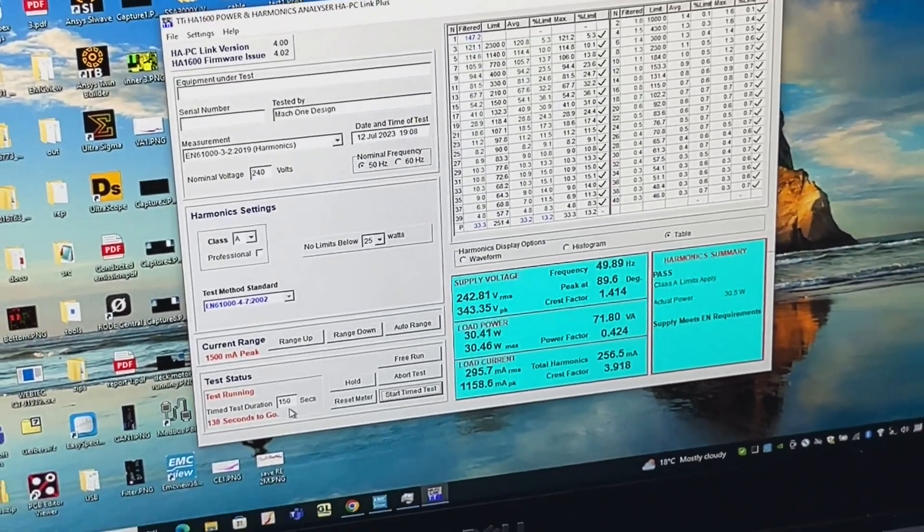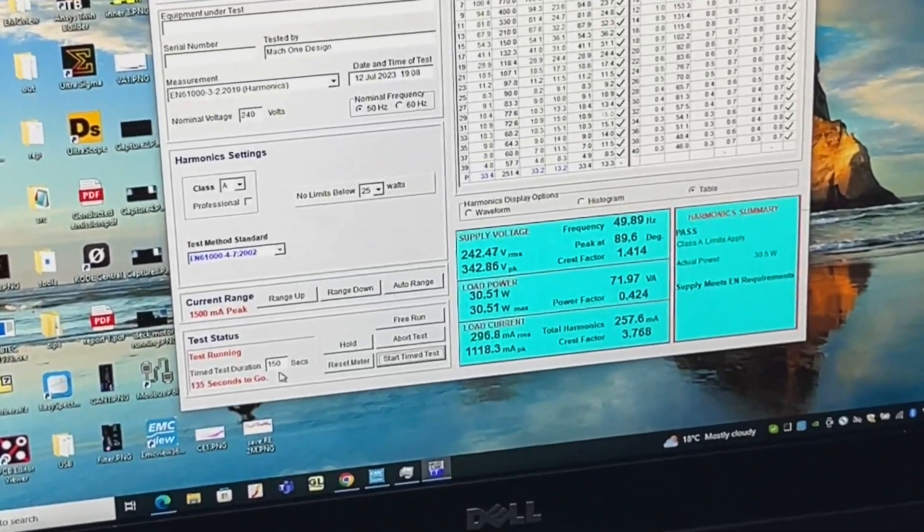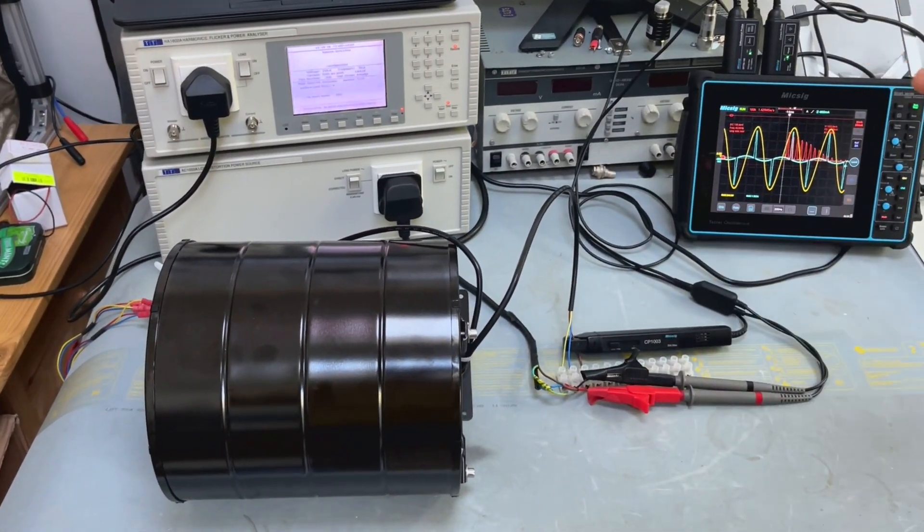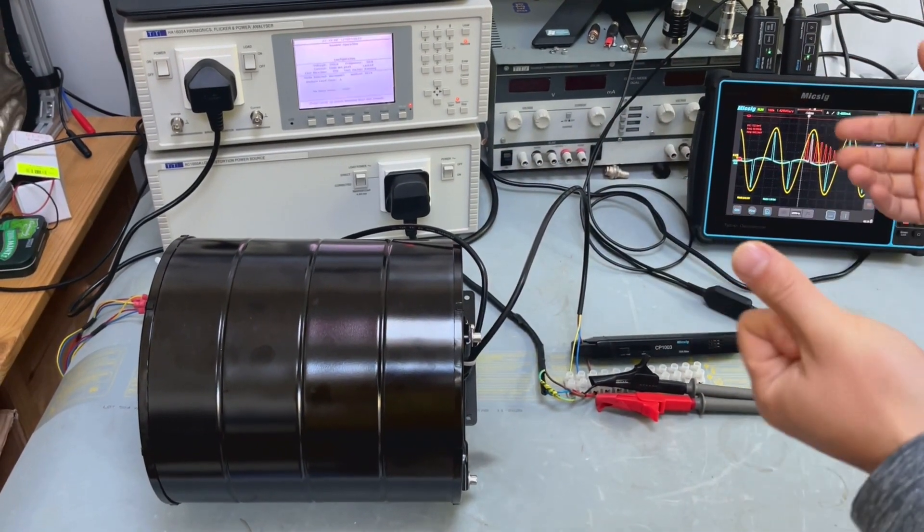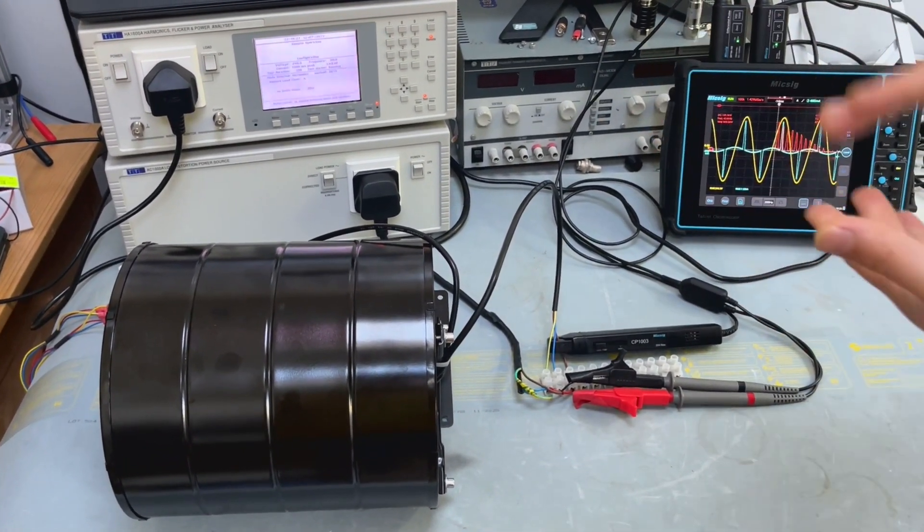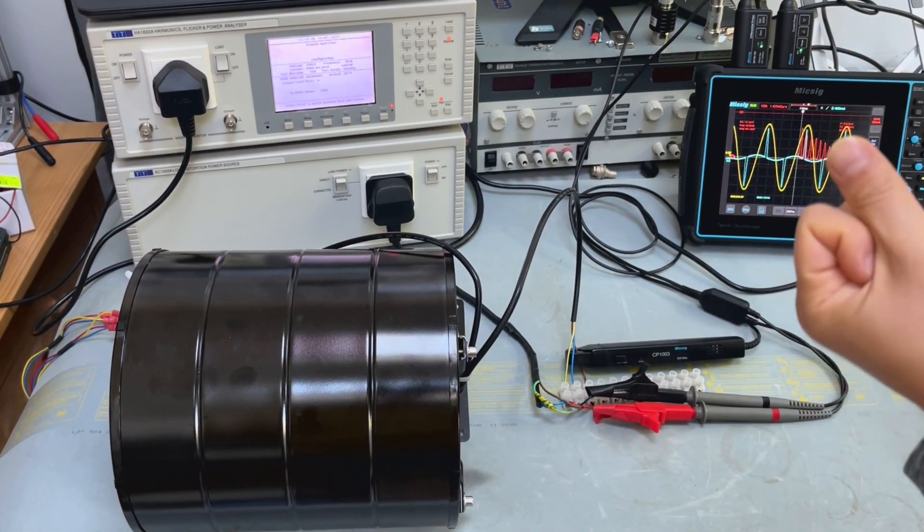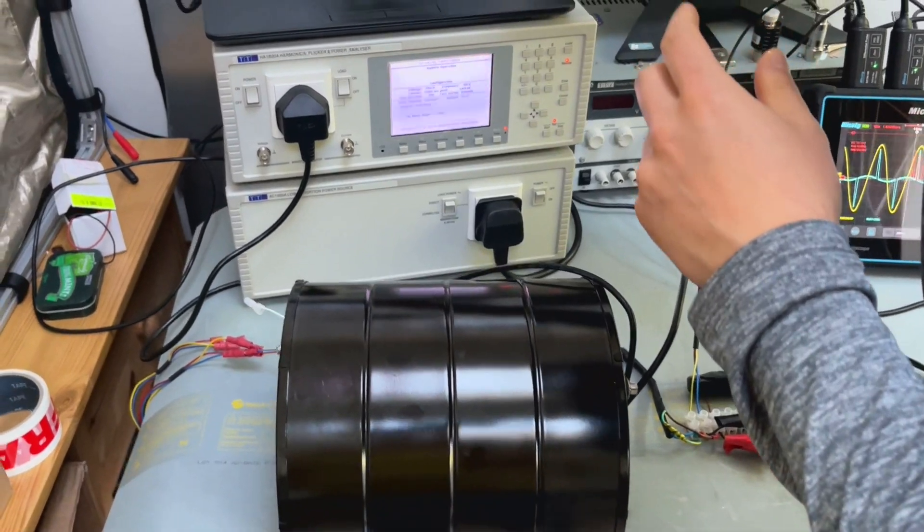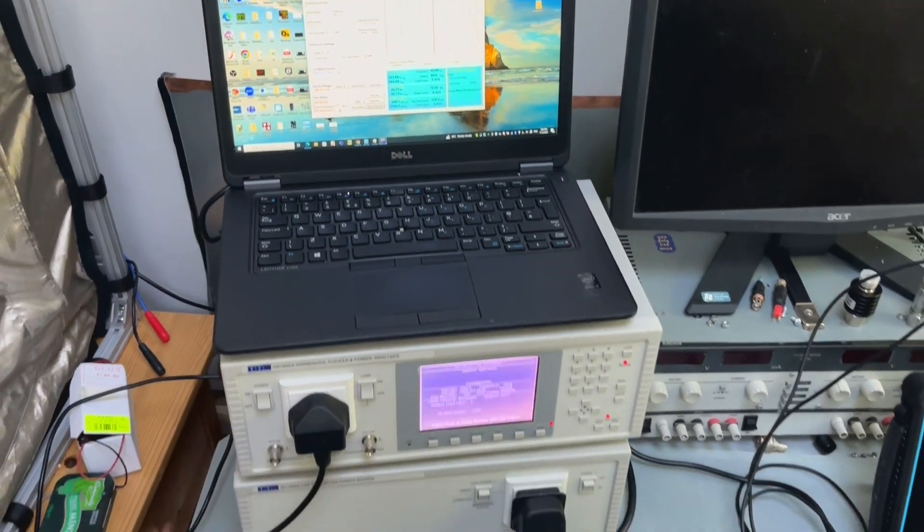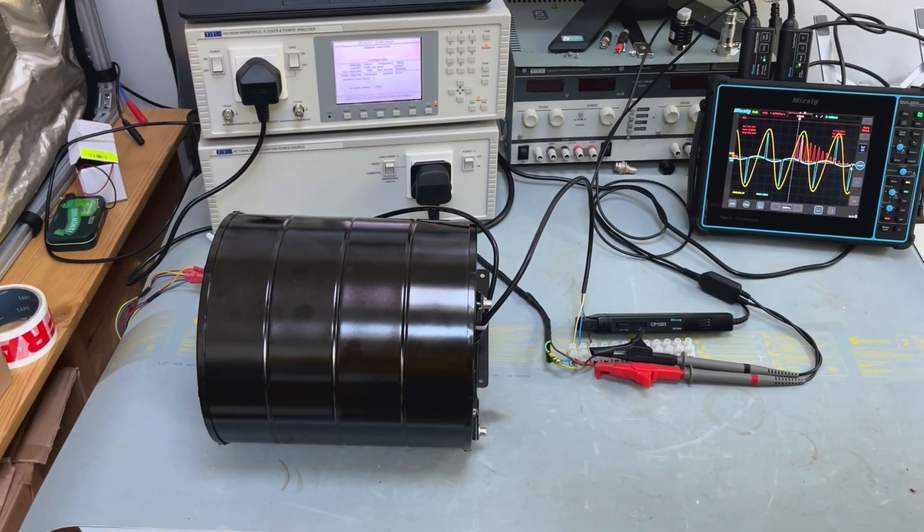You might wonder why do we need to perform the test across a few minutes. It's really because for this product is all right because it's quite steady, but for other products you might have different running states drawing different levels and different shapes of current. So by having a window that would allow you to test all the current conditions and once this test is complete it will give you a message that then you can produce a report as you will see.